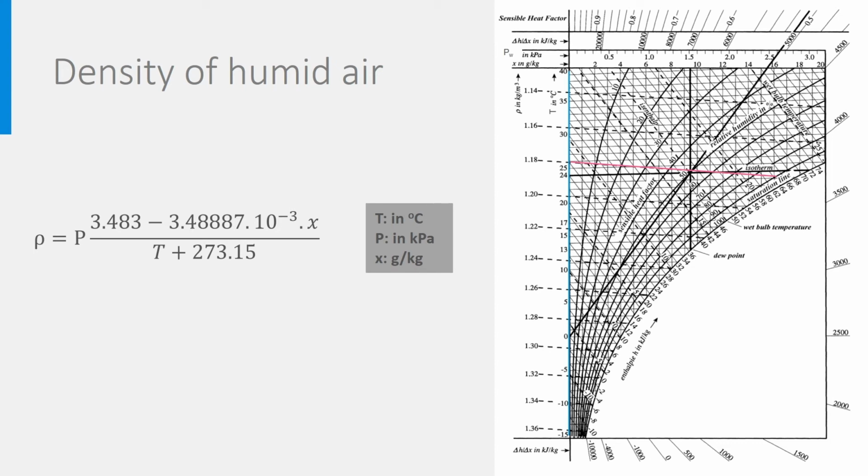At 21 degrees Celsius, you recognize the density ρ of 1.2 that we mostly use when making ventilation calculations on dry air, like you can learn in the course Energy Demand. You can also observe that at constant temperature, the density of air decreases when the water content increases. So dry air is denser than humid air.